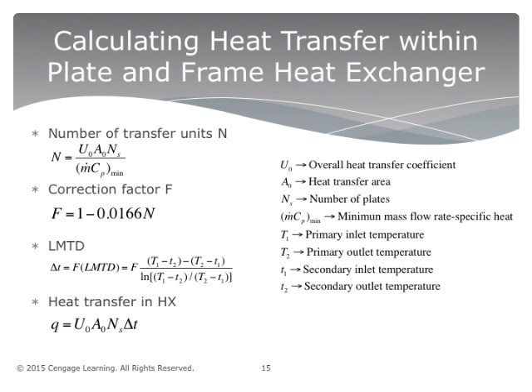To solve for the heat transfer, the log mean temperature difference can be used if the flows are either entirely counterflow or parallel flow. However, otherwise a correction factor is calculated to solve for the log mean temperature difference. The correction factor is indicative of how efficient the exchanger is thermally. To solve for the correction factor, we must first solve for the number of transfer units using the equation shown here. Then plug in the value for N and solve for the correction factor. If the flow through the exchanger is entirely counterflow or parallel flow, then delta T would be the log mean temperature difference. Otherwise, delta T can be solved by multiplying the correction factor with the log mean temperature difference of the counterflow or the parallel flow. Finally, we can solve for the heat transfer within a plate and frame heat exchanger.